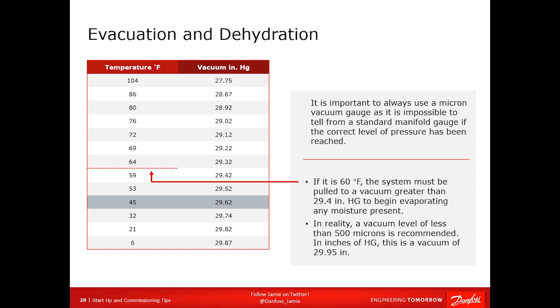Now, if you live in a warm climate, there's a good and bad part to it. The good part is it's a lot easier to dehydrate and evacuate when it's 100 degrees outside, because water at 100 degrees boils at a much higher pressure than it does at 40 or 45 degrees. All right, so it'll be quicker. The bad part is the air holds about 3 times as much moisture. So if the compressor is open and you take off to go grab a sandwich, you are going to saturate that oil pretty quick when it's hot and humid out. All right, so use a micron gauge. You'll never tell the vacuum level with a manifold gauge.